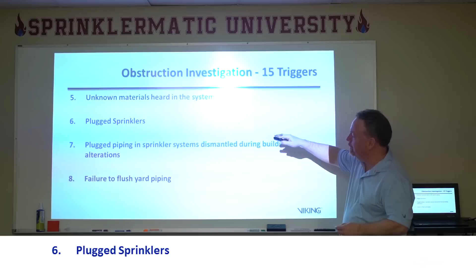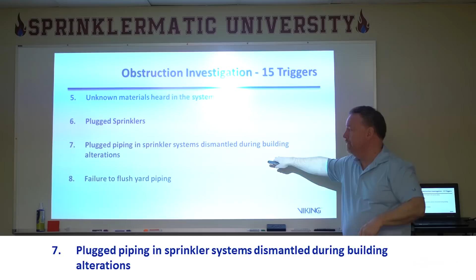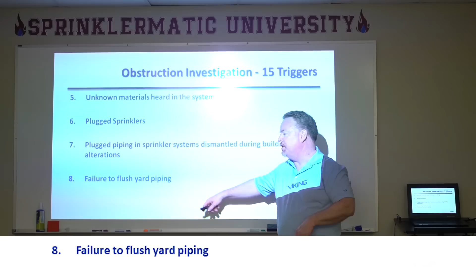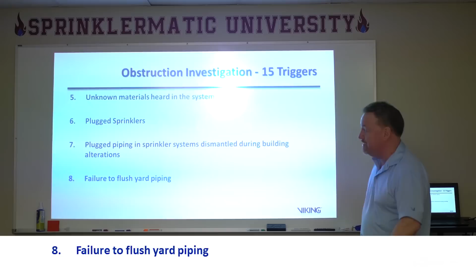Plugged sprinklers or plugged piping in the sprinkler system when you're dismantling during any kind of building alteration. If you're starting to do tenant work in a building, you pull the system apart, and you've got plugged piping and evidence of an obstruction, then you're going to do the rest. Failure to flush the yard piping: if you've got a yard system serving the building and it hasn't been flushed, you're going to need to do an obstruction investigation.